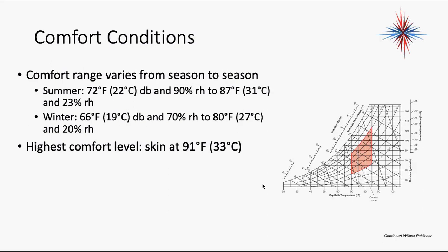Comfort conditions. This is the same chart I drew up there yesterday. They just chose to follow the curved lines, which I didn't really do because I can't draw curved lines very well on the tool that I have. Comfort ranges vary from season to season. In the summer, we're talking 72-degree dry bulb and 90% relative humidity to 87-degree and 23% relative humidity. Those are our comfort ranges.